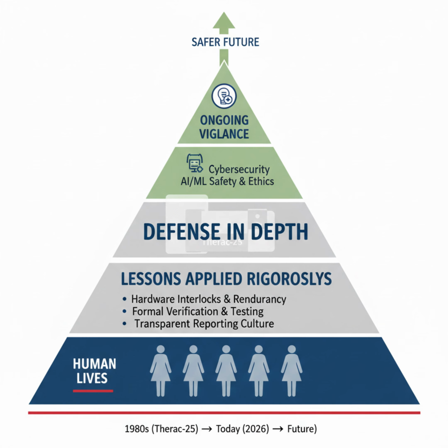2. Testing cannot prove the absence of bugs. The race condition in the Therac-25 occurred only under specific, narrow timing conditions. Standard testing didn't find it because standard testing doesn't explore all possible states and sequences. For safety-critical systems, formal verification methods, mathematical proofs of correctness, and systematic hazard analysis are necessary.